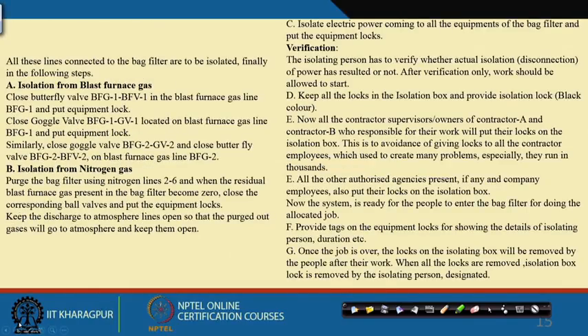The sequence has been written with named lines: blast furnace gas line 1 — close this valve; blast furnace gas line goggle valve — close; blast furnace gas line 2 — close. Then close the nitrogen valves. Then isolate the electric power. Then verify — by checking inside with gas meters whether gas is coming or not.